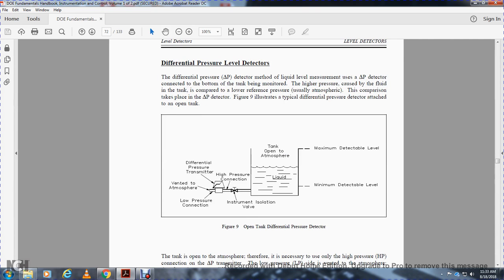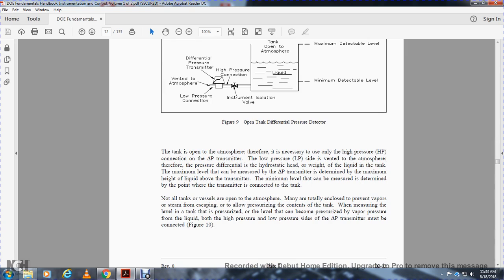Figure 9, open tank differential pressure detector, shows the maximum detectable level and minimum detectable level. The tank is open to the atmosphere, and from the bottom you see the differential pressure transmitter, the high pressure connection, the instrument isolation valve, and the venting to atmosphere low pressure connection. Since the tank is open to the atmosphere, only the high pressure side of the differential pressure transmitter needs a connection. The low pressure side is vented to the atmosphere, so the pressure differential is the hydrostatic head, or weight, of the liquid in the tank. The maximum level that can be measured is determined by the maximum height of the liquid above the transmitter. The minimum level that can be measured is determined by the point where the transmitter is connected to the tank.